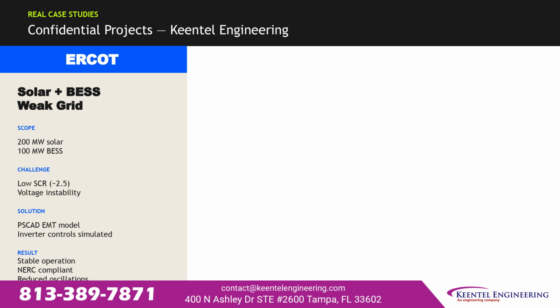Three confidential Keentel projects, real results. ERCOT: a 200 megawatt solar plus 100 megawatt BESS project on a weak grid with a short circuit ratio of approximately 2.5. Voltage instability was the presenting problem. Keentel built a PSCAD EMT model with full inverter control simulation. Result: stable operation, NERC compliant, oscillations reduced.